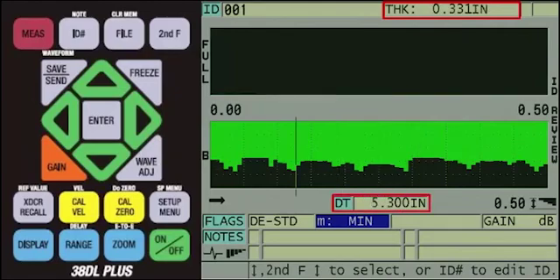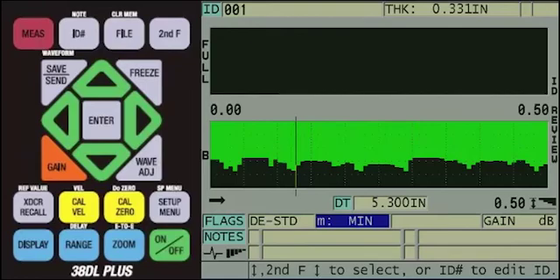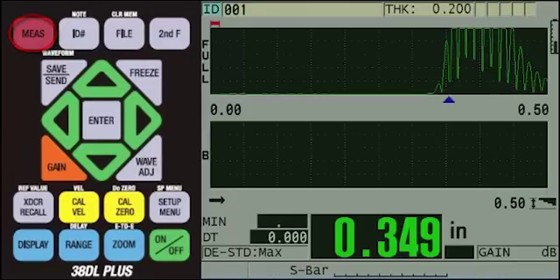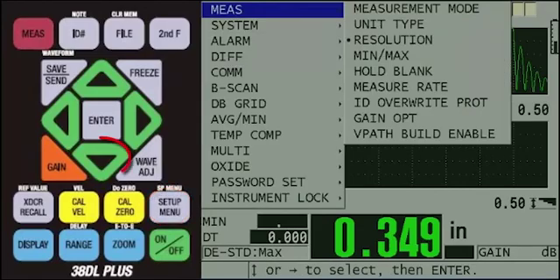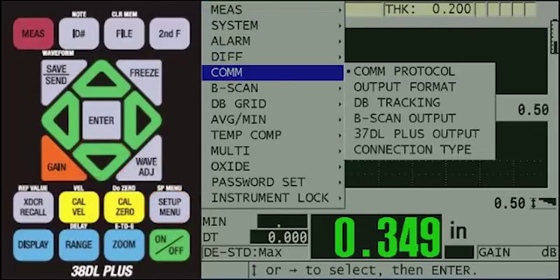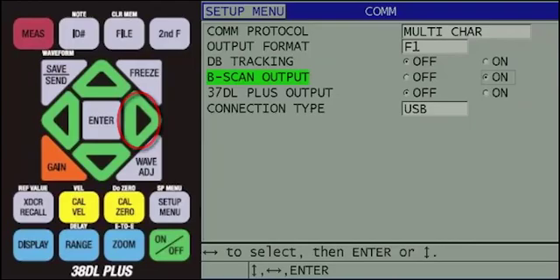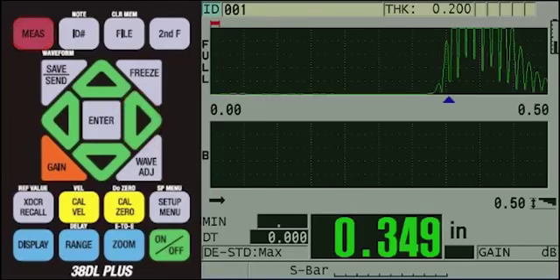If you then connect the 38DL Plus to the GaugeView Thickness interface program, you can transfer the B-Scan file and review it within GaugeView Thickness. In order to transfer the B-Scan data, you first need to turn on the B-Scan output in the communications setting of the 38DL Plus. To do this, first press the red measure key to exit ID review, then press the setup menu key, then keep pressing the down arrow until you highlight COM, and then press Enter. Then press the down arrow to highlight B-Scan output, then press the right arrow to turn it on, then you can press the red measure key. You can now transfer the file into GaugeView Thickness.